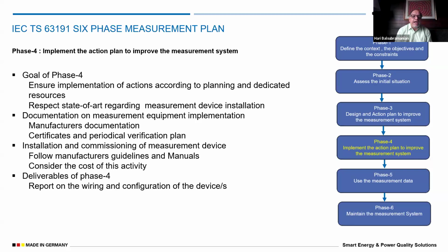Then the installation and commissioning of the measurement devices starts. Ultimately, whoever you're buying these devices from, follow the manufacturer guidelines and manuals clearly. Generally many customers do not read manuals, they think that if I know S1 and S2, I can connect the CTs S1 and S2, if I have V1, V2, V3, I connect the voltages and it's done. But it's always better to understand the manual, which becomes helpful in doing this.